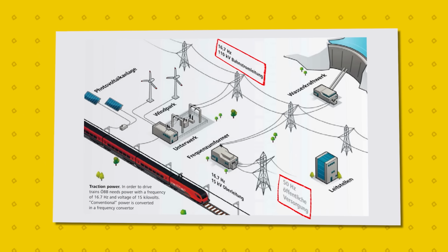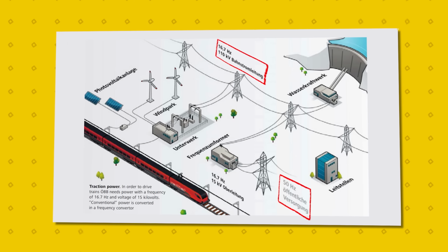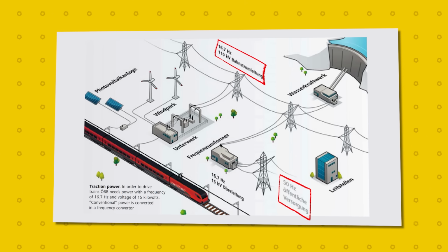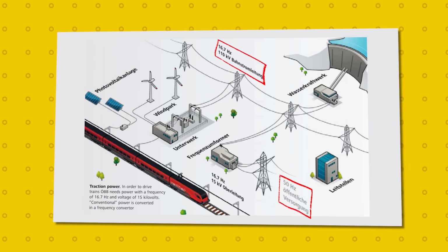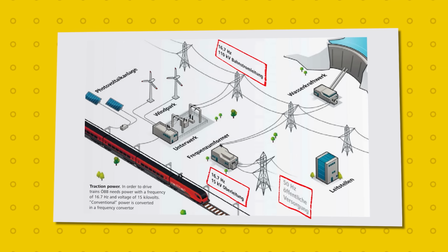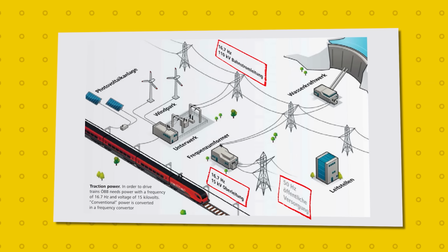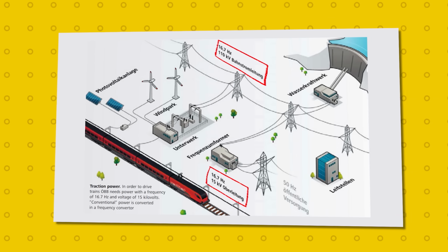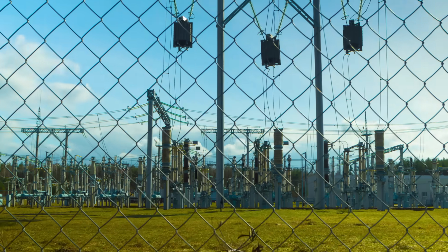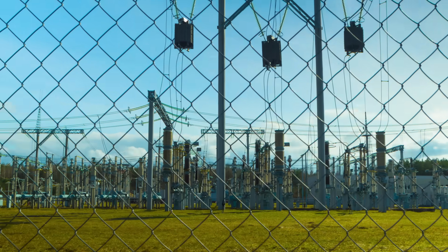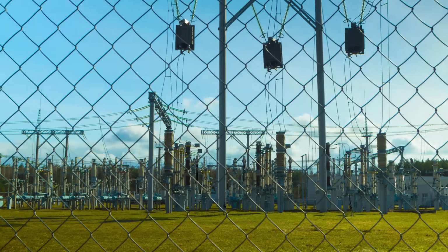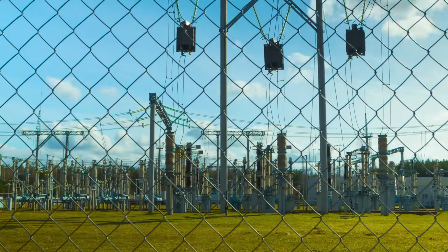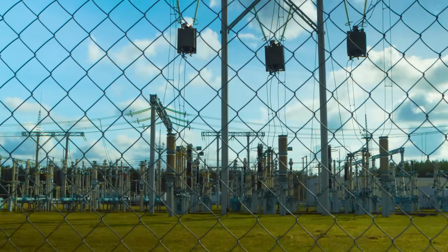Once converted, the power is transmitted through ÖBB's internal high voltage grid and delivered to local railway substations, where the voltage is reduced to 15 kV before being supplied to the overhead catenary system. Across Austria, 65 such substations are strategically distributed along the railway network to maintain consistent and reliable power delivery.